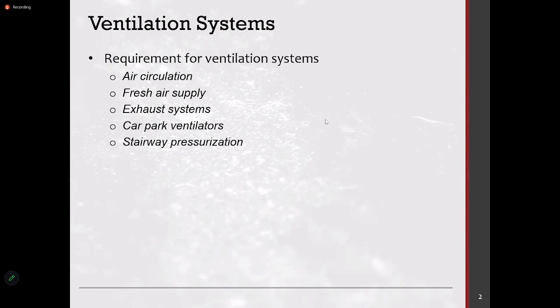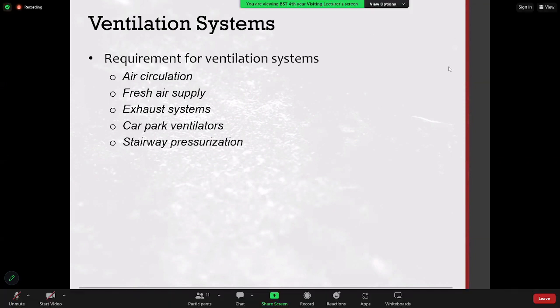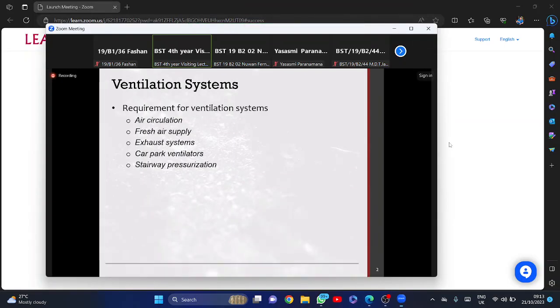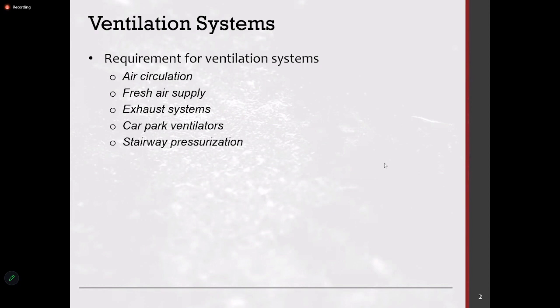So the second point is exhausting. To balance the space, you have to exhaust. Otherwise, the room will, like a balloon, increase in pressure, and that will also be uncomfortable. Exhaust systems can also be toilet exhaust systems, where you have to remove the odor, which is generated due to maybe hydrogen sulfide or whatever the pollutants. So you run separate exhaust systems for places like public toilets, where the usage is high and you cannot control it, and where sometimes they are not exposed to the outside. They are in a very inner part of the premises, so there is no breathing space for the room.